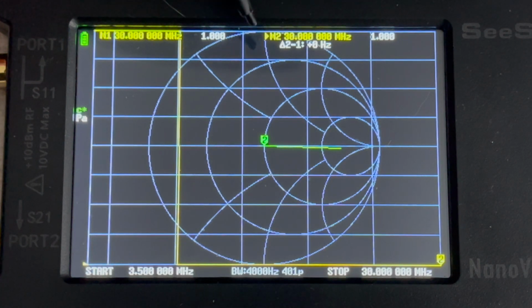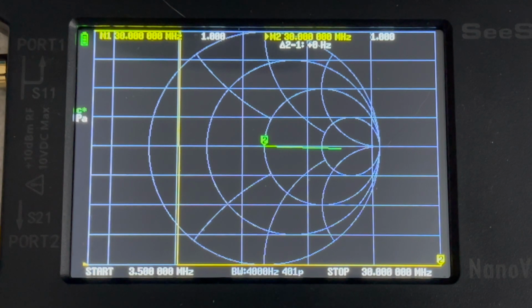Okay, in here, in yellow, in this particular case, normally it would be two different colors, but I haven't bothered setting anything yet. You will get information in the yellow, or whatever color the trace you have active, the channel, like we'll say channel S1, S2, format. It'll tell you the format and what the scale is, and then the current value. So you have 4 pieces of information on that one line. So if you want to know how to read it, the current value would be the figure at the end. So that's, generally speaking, probably what you're going to look for.